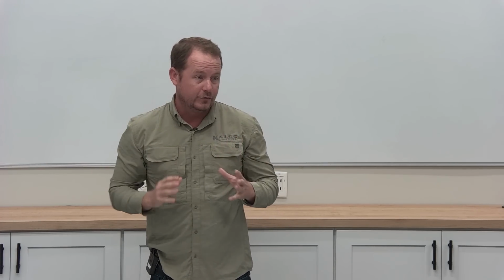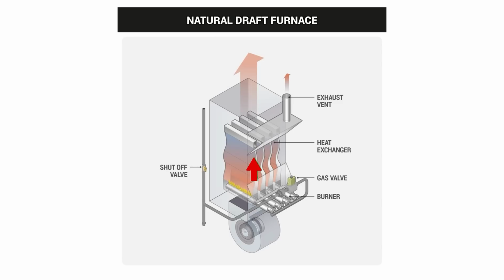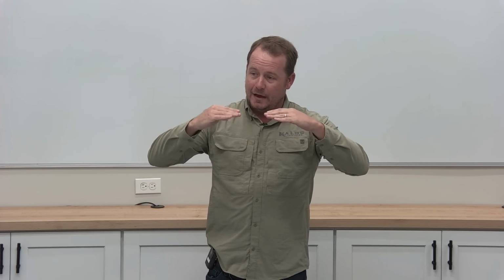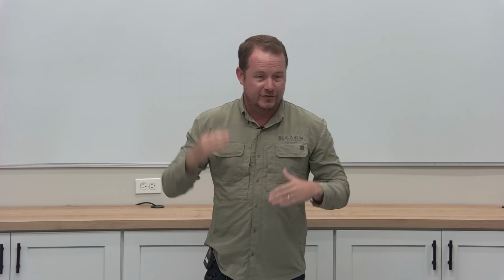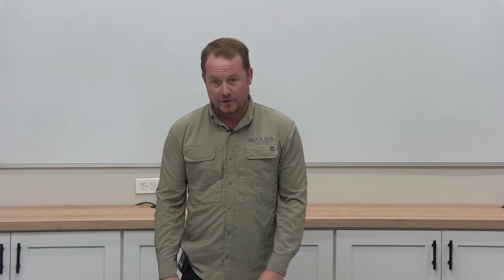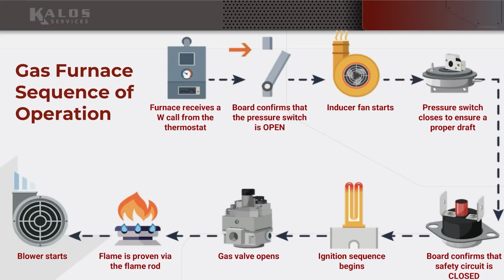And there's no power venting. There's no induced draft. All it does is you just have these very simple heat exchangers, and the heat rising is what actually brings it out. It's like a water heater, same way a water heater works. You don't have that. The reason why we have it nowadays is because we have these heat exchangers that are much more complicated, either tubes or they're like built into plates. And so because of that, we have to bring some air in to that furnace. So back to sequence of operation, W call, make sure that it's open, then inducer fan starts, then the board says, now this pressure switch better close, right?